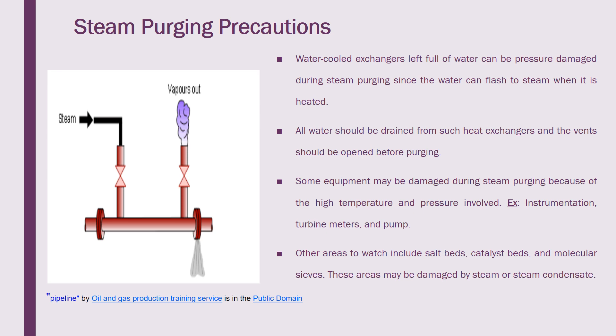While doing steam purging, we must clear 100% of the process fluid, operational fluid, or coolant fluid inside the tube or shell side of the heat exchanger. All water should be drained from the heat exchanger, and vents should be opened before purging. Some equipment may be damaged during steam purging and must be isolated - such as instrumentation, turbine meters, and pumps - and these must be isolated from the steam purging area.